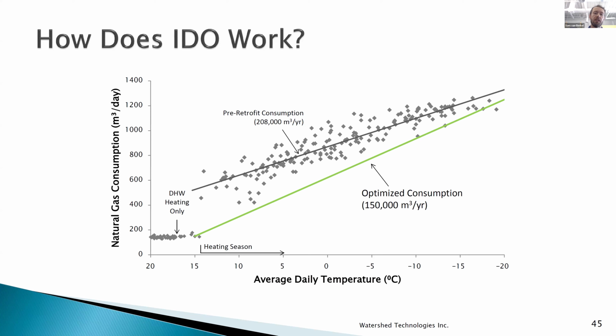And then what we do is we plot a line from the balance temperature of the building, which for these buildings is typically 15, 16 degrees Celsius. And then we plot that line up to the coldest point. So we're not expecting the building to use less energy during the coldest part of the year, when it's minus 15, minus 20 outside. But we know that we can reduce the gas consumption in the shoulder seasons, all that period in between.